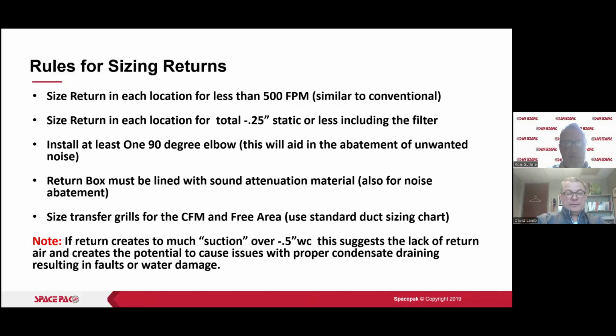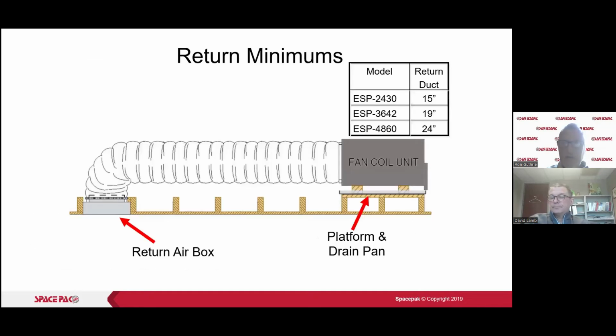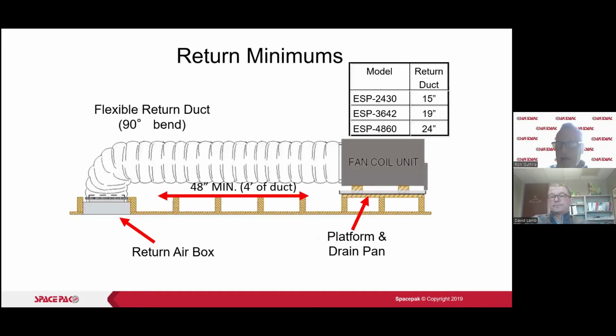Size transfer grills for underneath the doors in bedrooms, for instance. Make sure that there's room underneath the doors for what return we do need to make its way into the area that will be used for a common return. Okay, there's that 90-degree bend. All right.